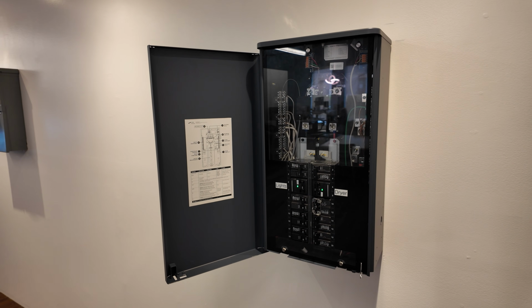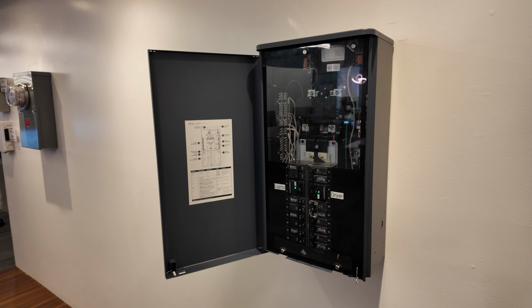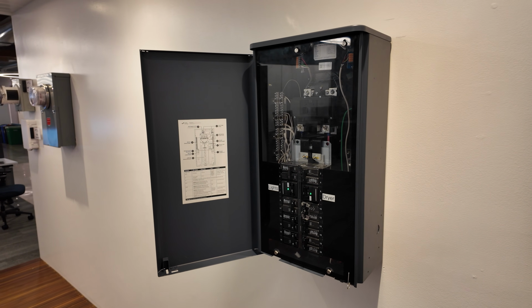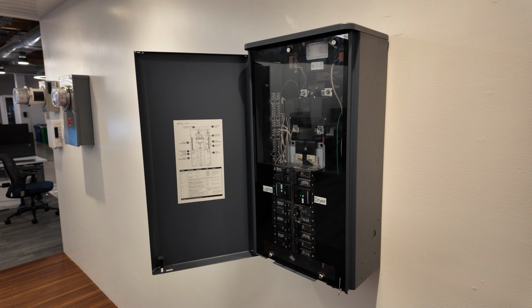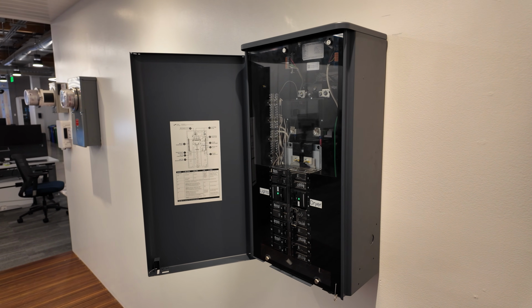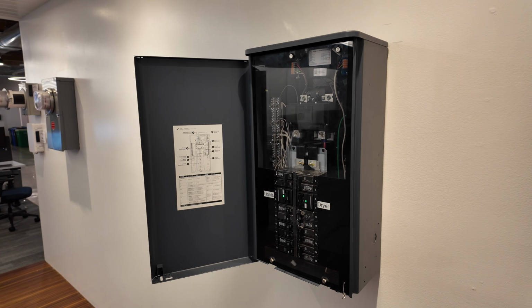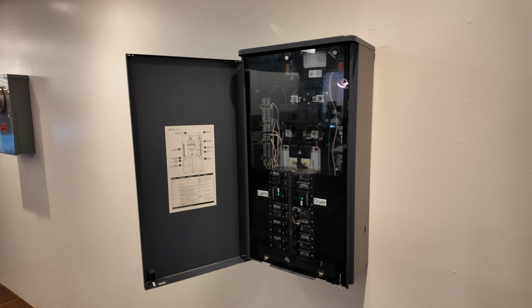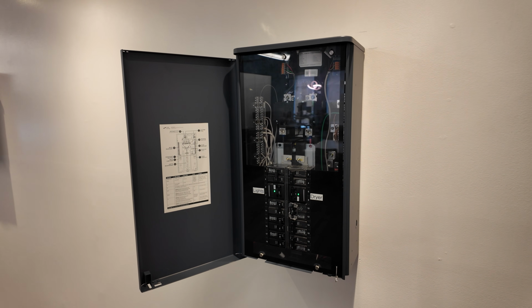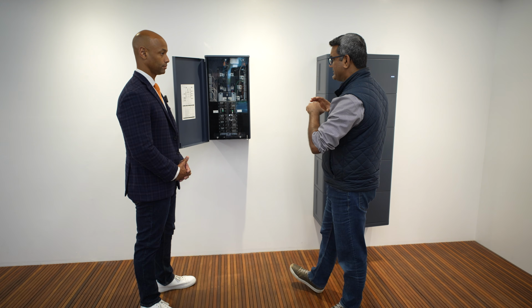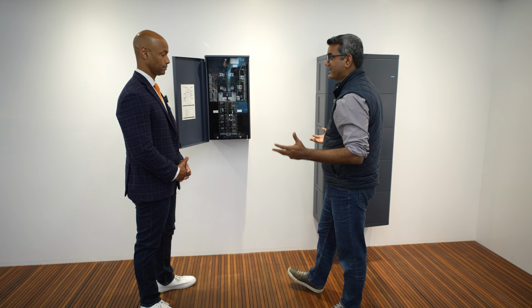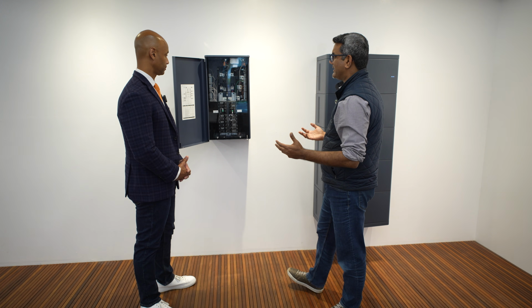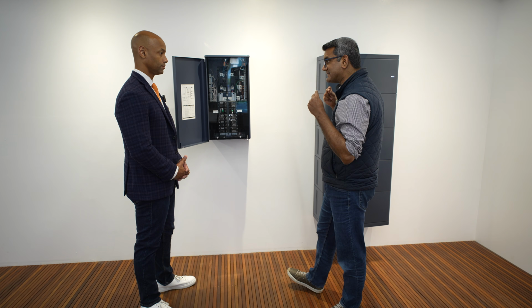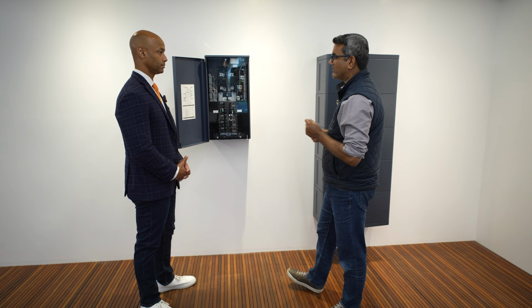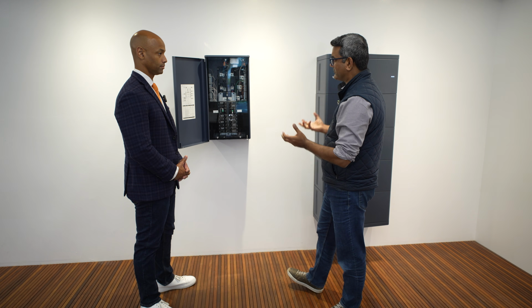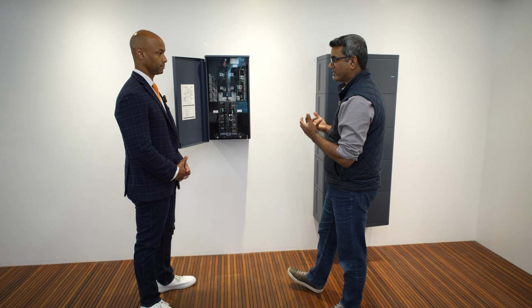It also does all the metering for the grid, always watching it, because the moment the grid voltage or frequency sags or rises, it takes the home off grid. That's why, as you'll see in the demo, our backup is seamless. The customer doesn't even realize the home is backed up, because we react instantaneously to grid fluctuations. That's the secret special sauce in our firmware.